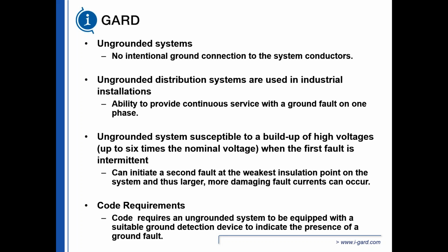Ground fault detection is measured as each phase potential to ground. If you have, for example, a 480 volt ungrounded system, you're going to measure 277 volts from all phases to ground on a healthy system. When one of the conductors touches ground, the potential between that conductor and ground is 0, and the potential between the unfaulted conductors and ground becomes 480 volts.